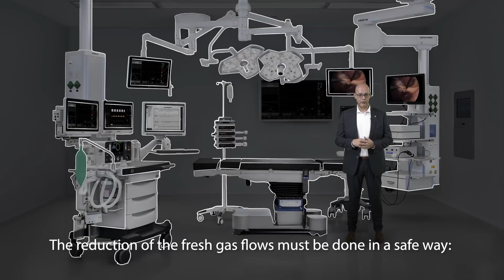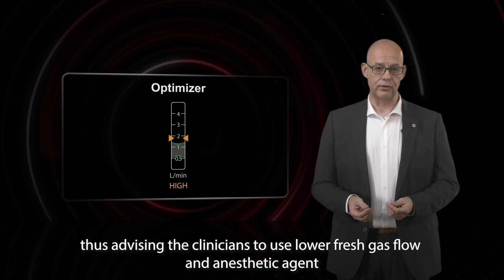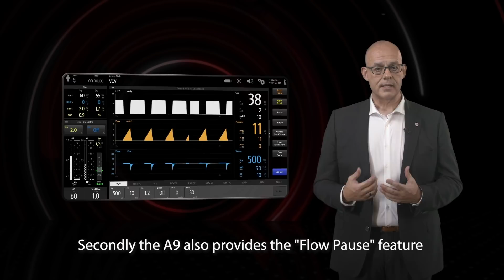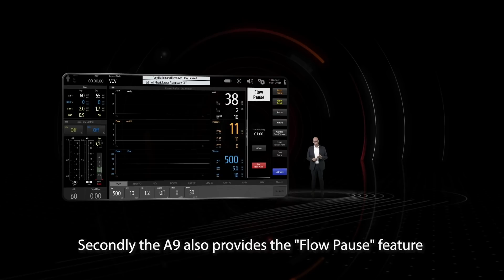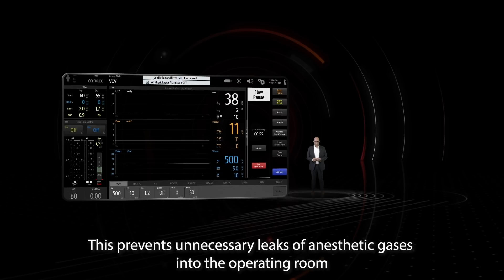First of all, we have integrated ACA, Automatic Controlled Anesthesia Function. This offers you the best reduction of waste gas with the least intervention from the medical staff. For situations in which you don't want or need the ACA function, we also have the optimizer. The optimizer indicates the optimal fresh gas flow rate, thus advising the clinician to use lower fresh gas flow and anesthetic agent. Secondly, the A9 also provides the flow pause feature to stop the fresh gas, ventilation and alarms temporarily.